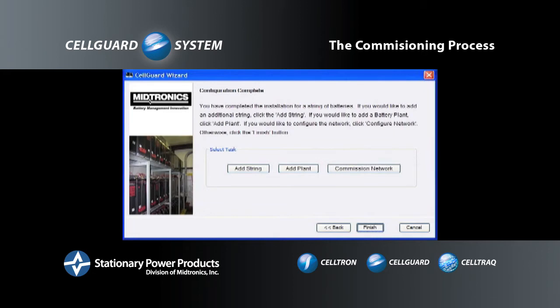At this point, the commissioning of the hardware for the string of 4 batteries is completed. There are 3 options in the wizard to choose from on this screen. If you need to add another string to the same battery plant, so it is a string that is in parallel or on the same bus with the string just commissioned and will share the same BCU, click on Add String. If you need to commission the hardware for a string of batteries that is on a different power plant, and it has its own BCU, then click Add Plant.